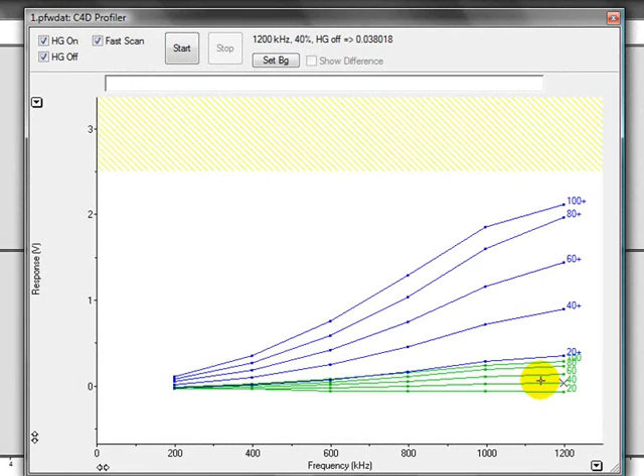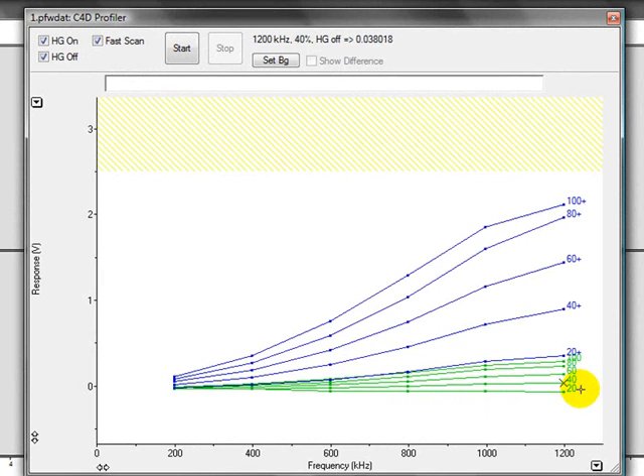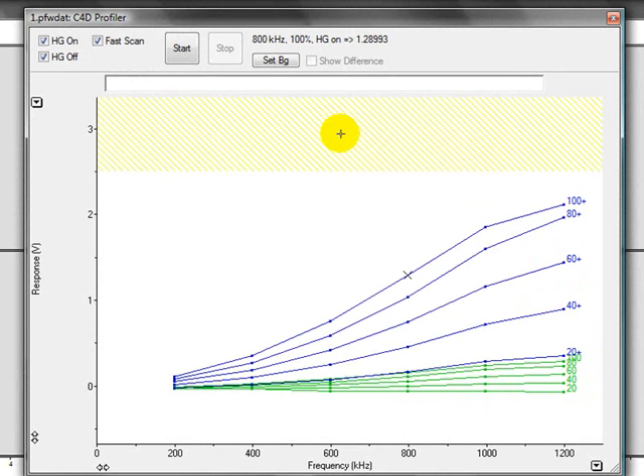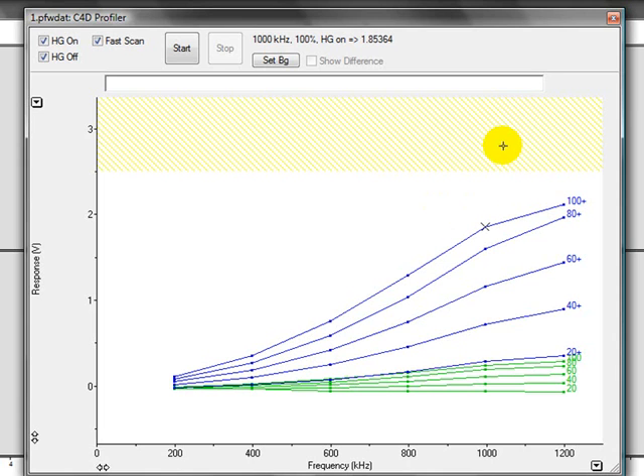Once the software is finished, you will have a series of plots where the software has analyzed different frequencies at different amplitudes. These are the ones with the head stage gain off, these are the ones with the head stage gain on. This shaded part is where the detector has saturated. You should ignore any plots that go into this area.